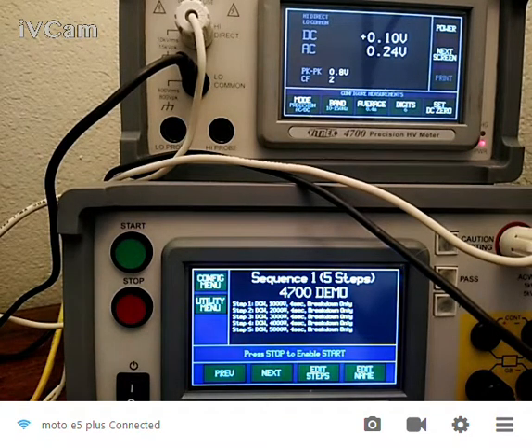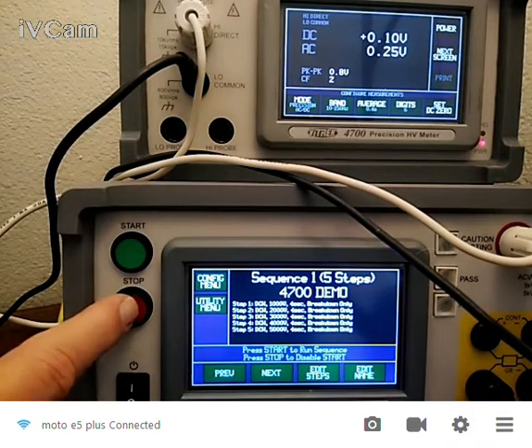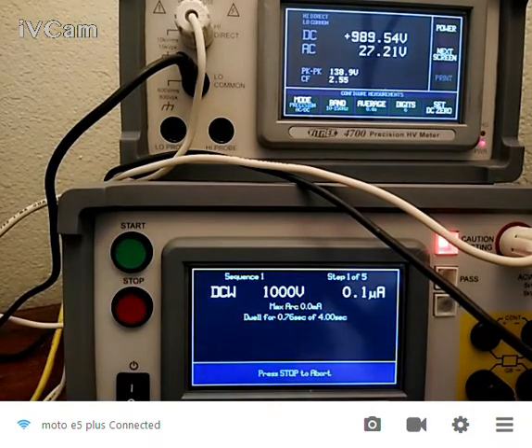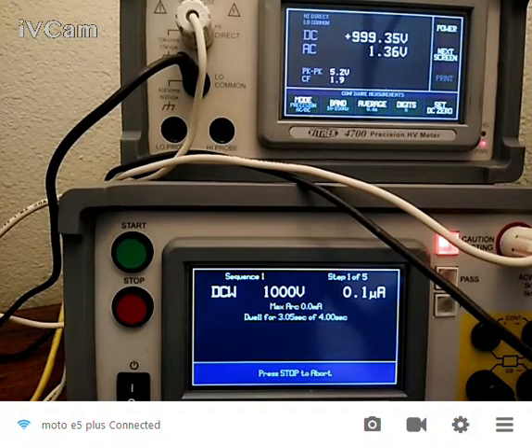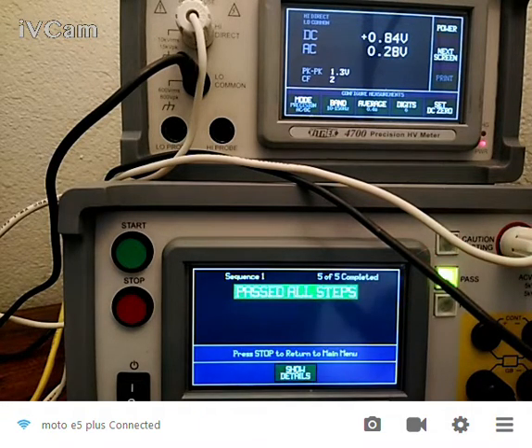So I've got the hipot programmed, and I'm going to start it up, and what you'll see is it's got several different levels. It's designed to go right now to 1,000 volts and hold it for a few seconds, and then 2,000, and then 3,000. The AC you see on there is the AC ripple on the line. And there is the DC 4,000 and 5,000. So the hipot just goes up to 5,000 volts. The meter itself can have up to a 10,000 volt direct input.